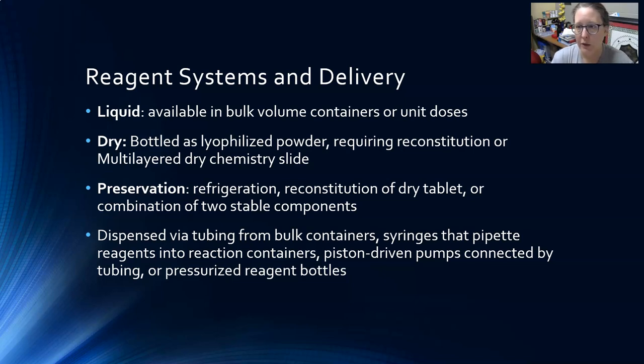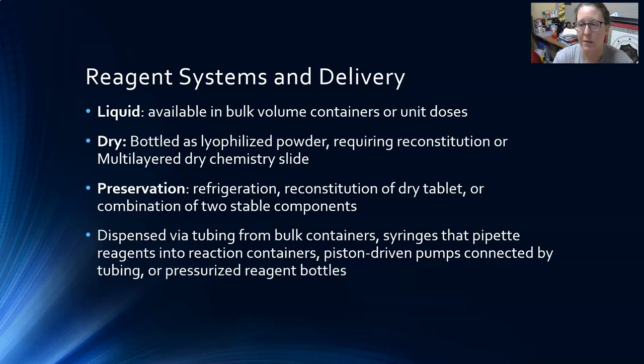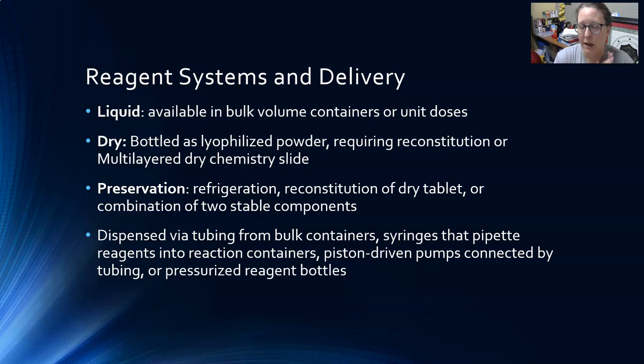Alternatively, it can be a combination of two stable components — the reagent cartridge has two blocks with Reagent A and Reagent B, which are stable if not mixed. A certain amount of Reagent A is added to the reaction vessel, then Reagent B is added, they mix to make the working reagent with limited stability, and then the specimen is added. Reagents are often dispensed via tubing from bulk containers, syringes, piston-driven pumps, or pressurized reagent bottles — the goal being to get reagents into a vessel for reaction with the sample.